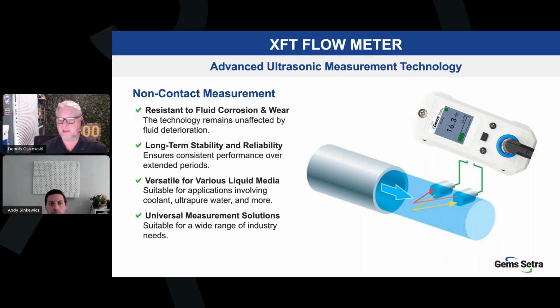Flow rates are displayed in intervals. That's called a damping coefficient. Five seconds is the default, so every 5 seconds the display is refreshed. That's also a parameter that you can set, that time constant. The longer the time you put in, the smoother it will read on your display. It ranges from a half second, when you want something more real time on the display, all the way up to 10 seconds. Okay, next slide.